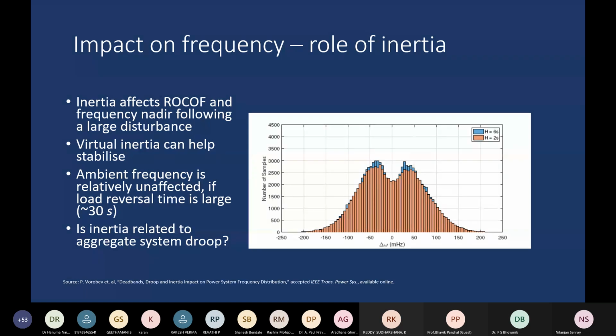Then what affects the ambient frequency? So this is a probability distribution. It's basically a histogram plot of the ambient frequency collected over 24 hours. And here it shows a bimodal distribution. Now the bimodal distribution is not always seen. For instance, if you do this study on the Indian grid, you do not see a bimodal distribution. But this particular graph is coming from the UK grid. It shows a bimodal distribution indicating that there is a frequency corrective action. That makes the frequency stay in the range of 50 Hertz, or in this case, the delta frequency remain in the range of 0 Hertz or 0 millihertz.